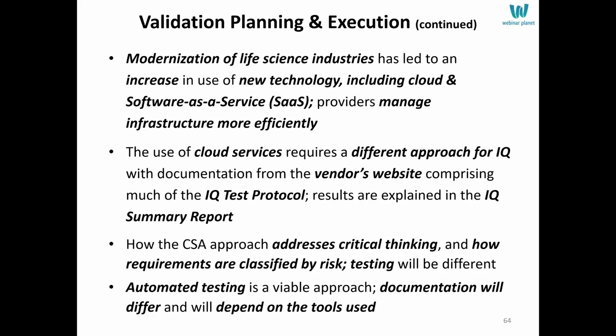And then if they give you test scripts, whether these are to be executed manually or automated test scripts, they must be able to tell you how that's done, and then you can decide whether there is one or more test scripts per requirement, and that it's robust enough based on the risk assessment of the requirement. So a lot of it can be delivered by the vendor, but you can't take the requirements or test scripts at face value. You must make them your own. You must vet the requirements and then vet the test scripts against the requirements you come up with.